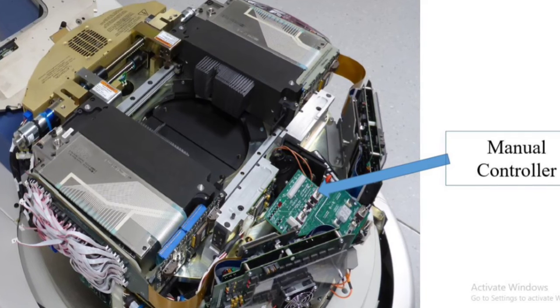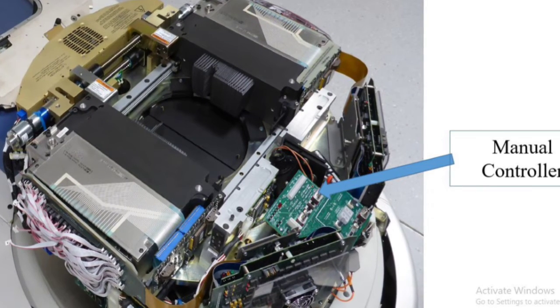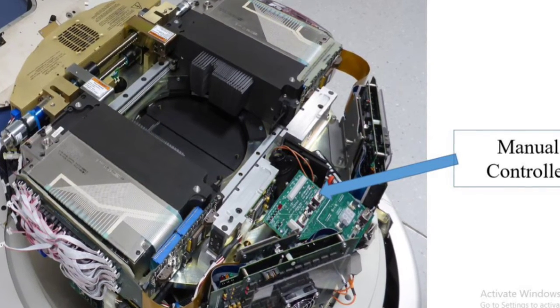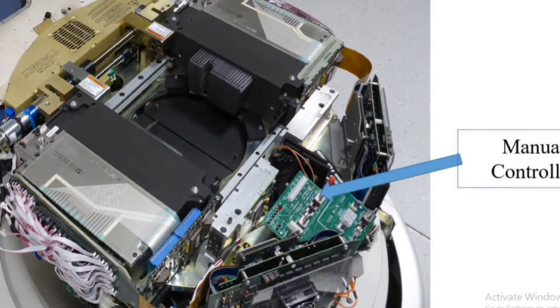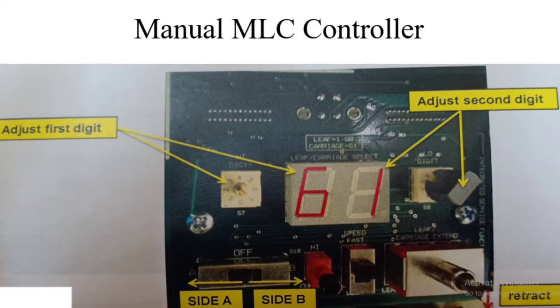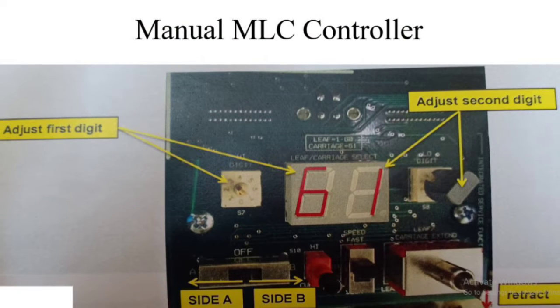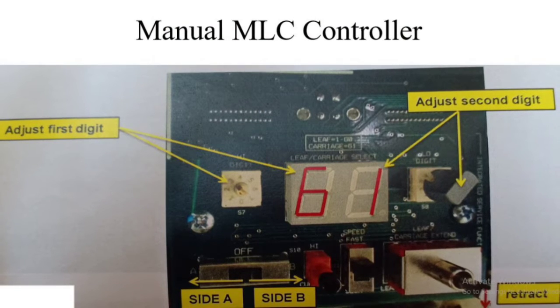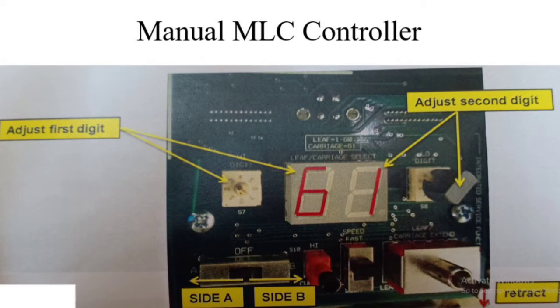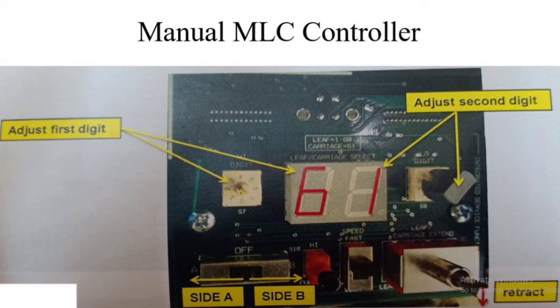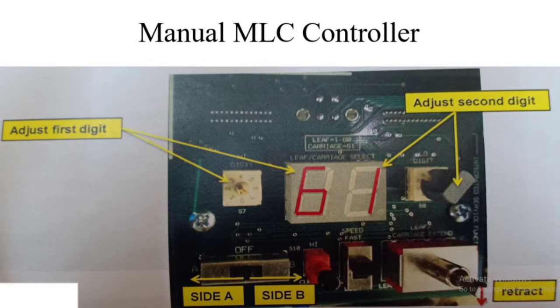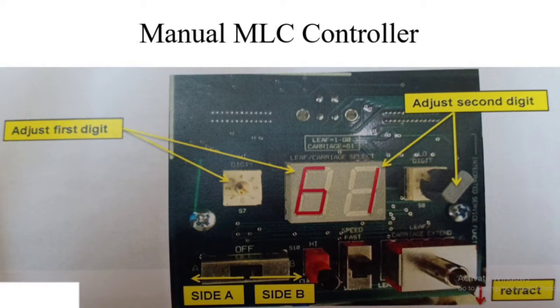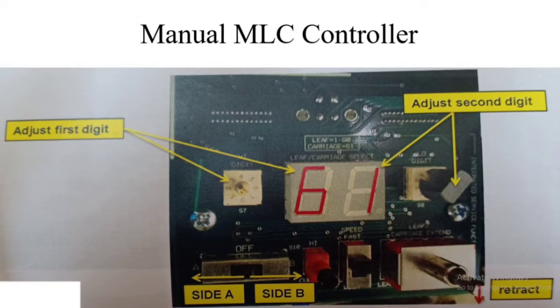Once you remove the collimator facet, you can see the manual controller of the MLC, through which you can move the MLC leaves manually, and you can also move the carriage manually. This is the MLC manual controller, and here you can select which bank. If the interlock comes in bank A, you have to select side A. If it comes in bank B, you have to select side B. And also you have to select the MLC leaf due to which the interlock has been raised.